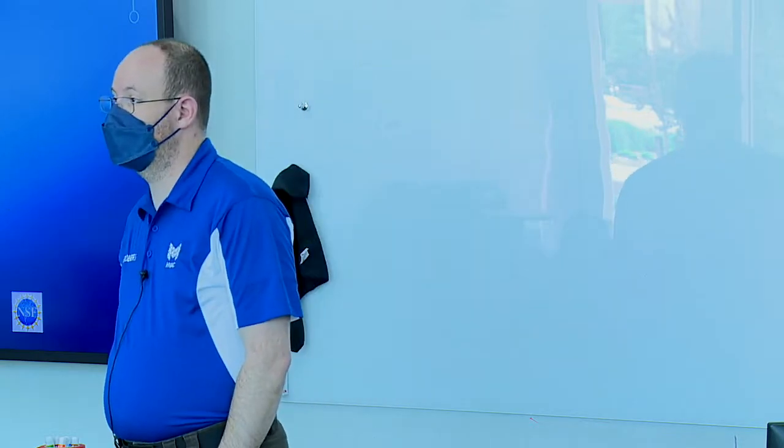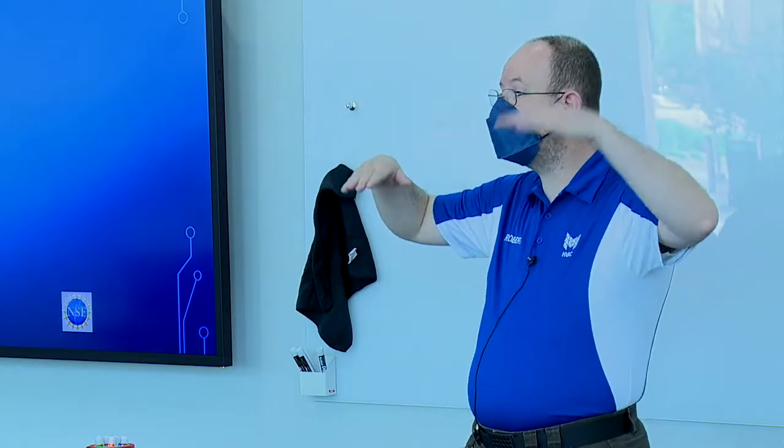this problem. Or finding little problems within buildings, like, is that room temperature sensor accurate? Dealing with sensor drift, dealing with discrepancies between two sensors that should be reading about the same number. Okay, why aren't they?